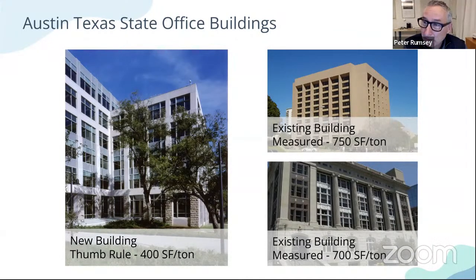But anyway, 400 square feet per ton meant we needed a very large cooling system. So we went and measured other buildings. Luckily, Texas A&M University, which was nearby, had been measuring state office buildings in Austin for several years. We asked them to show us the actual measured cooling requirement. The buildings were coming in at 750, 700, even 800 or 850 square feet per ton. These all result in actual loads that are half of what the thumb rule was telling that engineer to put in.